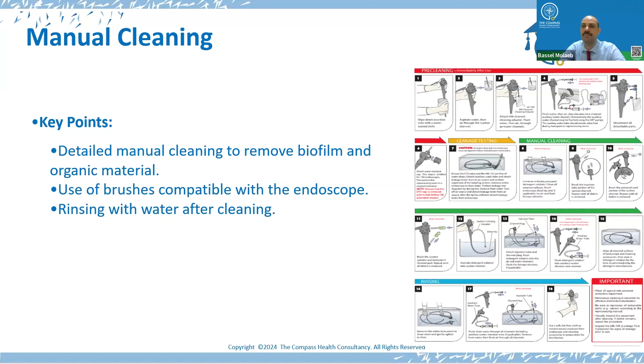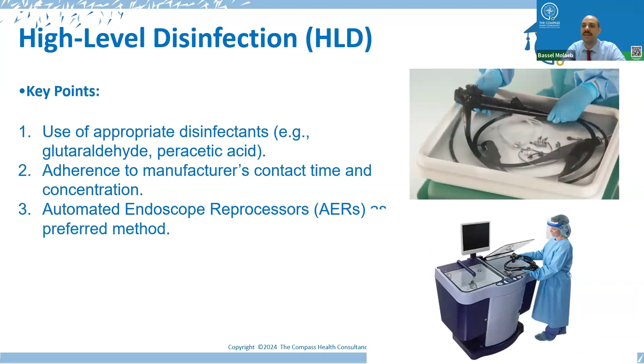So the next step would be the high-level disinfection. It is achieved either manually or through the automated endoscope reprocessor. AERs provide a superior cleaning and decontamination, improving the rinsing of disinfectants and reducing residual disinfectants in the endoscope as compared to the manual process. High-level disinfection is the recognized minimal standard for semi-critical flexible endoscopes according to the Spalding classification.